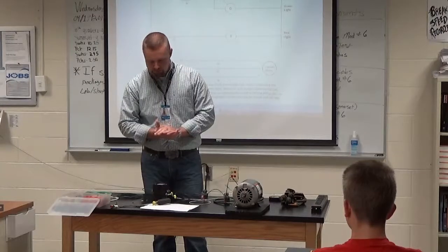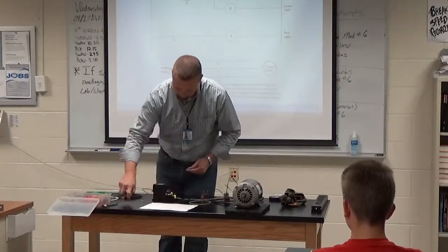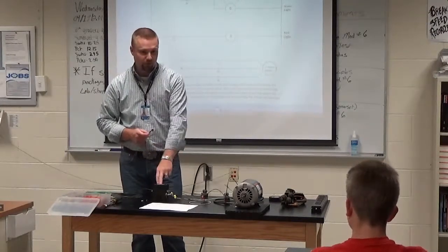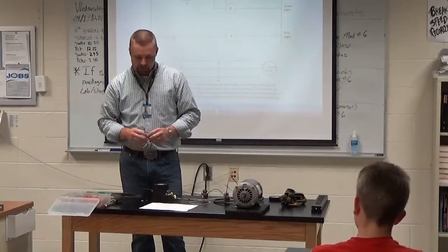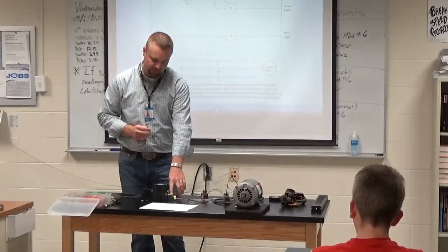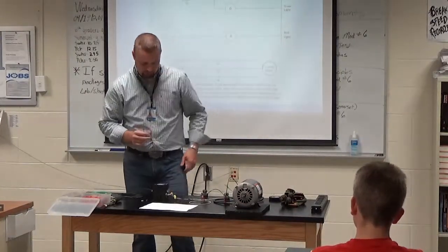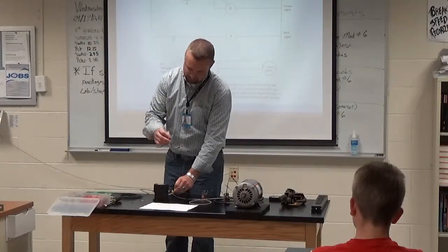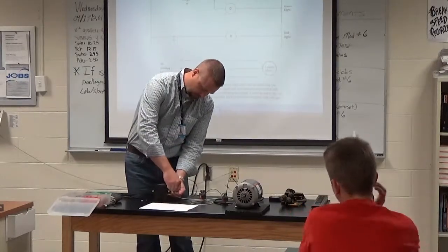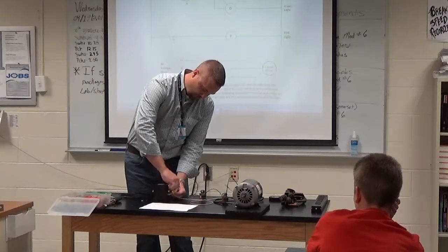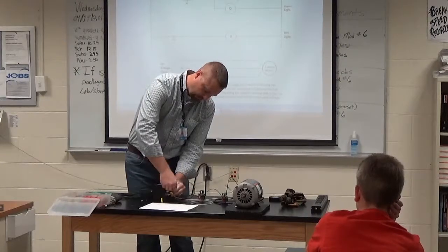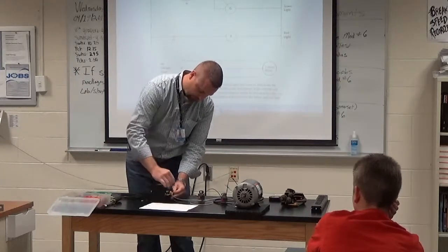The only thing left to do is insert our green light now. For this particular lab activity, we want the green light to indicate when the motor's running. So, I want to connect the wire to the green light from the coil of a motor starter, okay? Not the neutral side. You want to connect on the opposite side, wire coming from the start button, correct? So I'm simply going to take the cap off my wire going to my coil, twist it in with it, and reinsert the cap on that.